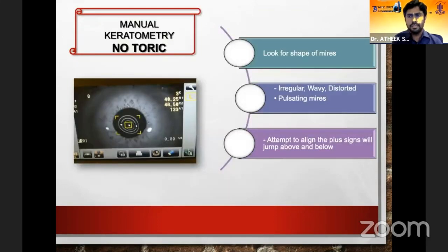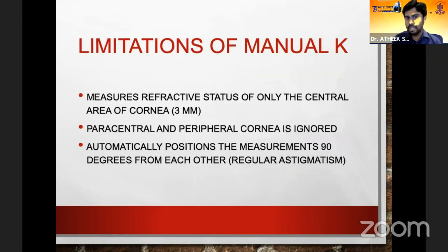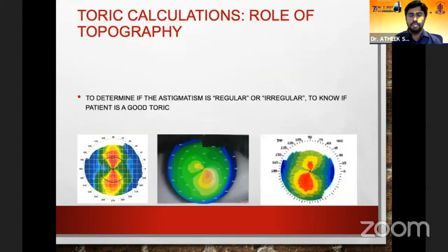Red flag signs in manual keratometry include the shape of the mires — if they are irregular, wavy, distorted, or you are unable to align them, these indicate that keratometry is unreliable. A key limitation of manual K is that only central K can be obtained and the peripheral cornea is ignored, which is where topography comes into play.